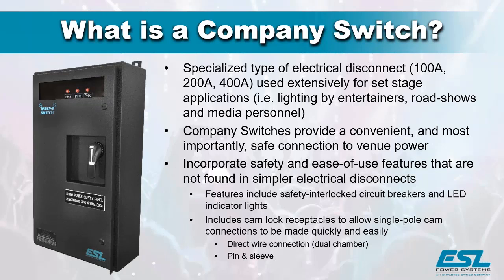The direct wire connection uses lugs behind the cams inside the company switch at the bottom, allowing for bare wire connections if they don't have the single stab cams. That's not a preferred method, and I try to talk people out of it as much as possible when talking to end users, because you'll eventually thrash those cables and have to trim them and deal with all kinds of issues. It's really nice to use the single pole cams instead, and our standard company switch actually comes with just the cam receptacles.